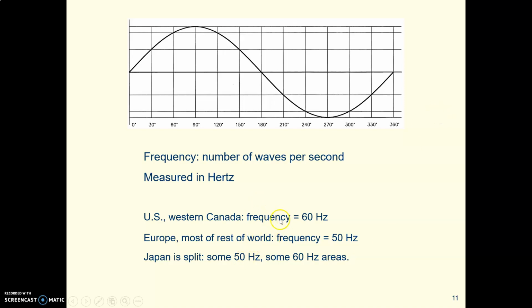It's interesting to know, and I've done this, if you take a motor rated to run at 60 cycles because it was made for the US or Western Canada, say an 1800 RPM motor, it will turn at that speed when plugged in in the US. If you take it somewhere like South America where the power is 50 hertz, that motor turned at 1500 RPM. It was 5/6 as fast, and that's what you call a derated motor. You just have to know that and account for what speed the thing will turn.